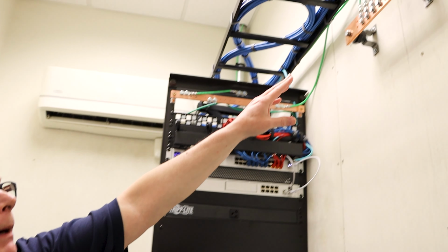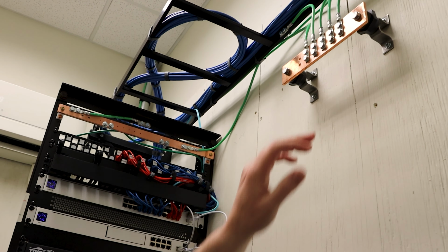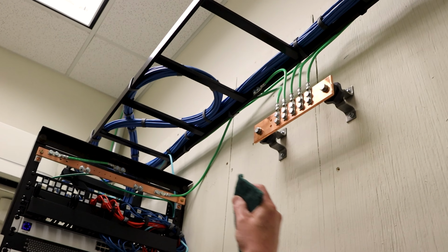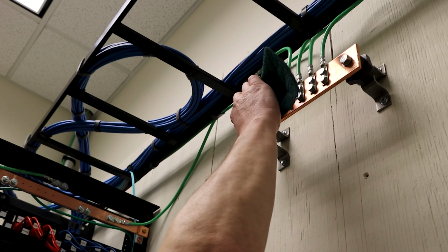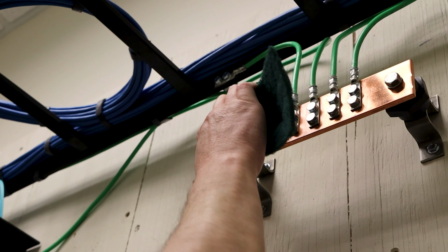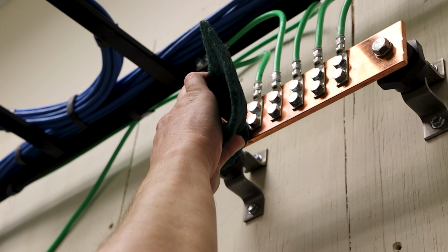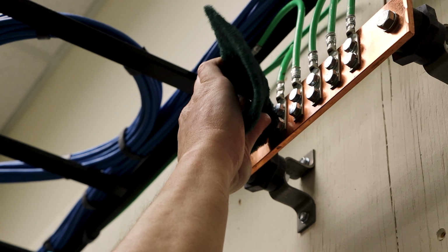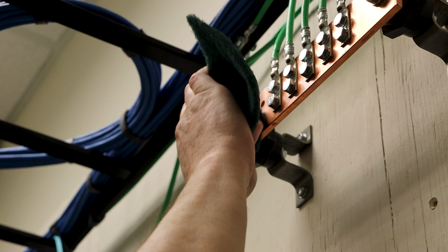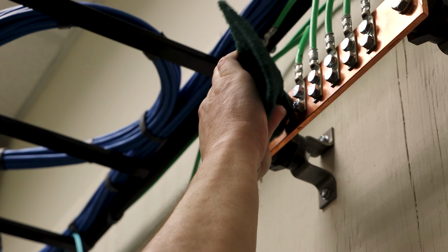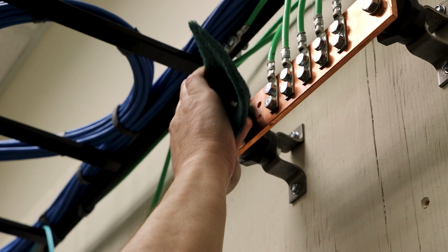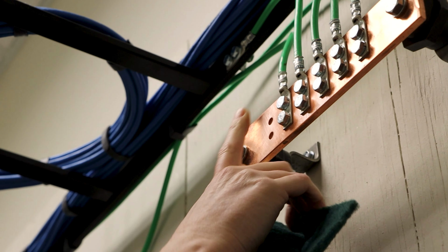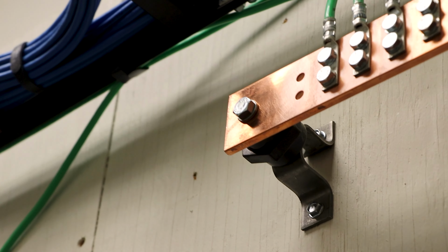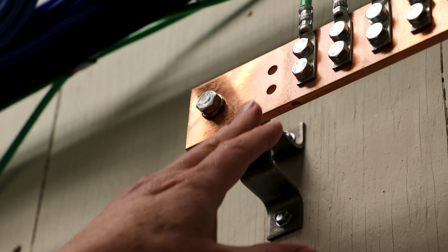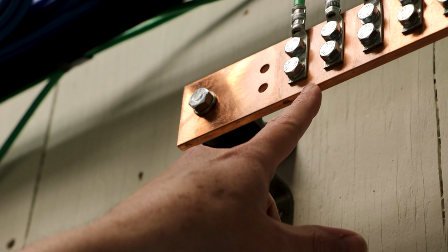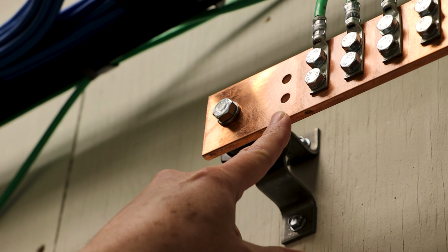For example, I'm going to prep up our spot on our bus bar here, and I'm going to show you, like using the Scotch-Brite pad, you want to get as much of the old oxidation or grease or anything that's on there off of there. So just polish it so that you get all the oxidation off and you got a nice, clean, bright surface. And as you can see, hopefully you can see it in the video, it's quite a bit brighter now here than it is here because this is already oxidized and that is not oxidized.